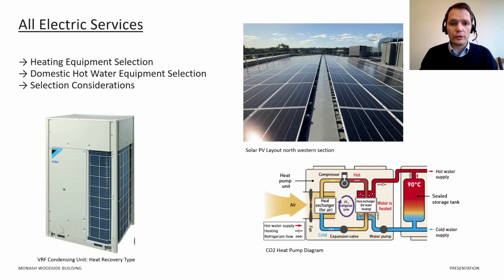Typically, gas is used for generating heating hot water and domestic hot water. This building uses VRF systems for heating and CO2 heat pumps for domestic hot water. During the selection of the system, practical factors such as plant footprint, maintenance access, and the ability to effectively reject the load were considered. The VRF system provided high efficiency performance in heating mode and a modular approach which gave us the ability to maximize the available roof space for the solar PV layout. The CO2 heat pump offered unparalleled performance during low ambient temperatures, and because it uses CO2 as a refrigerant, it has a global warming potential of 1.